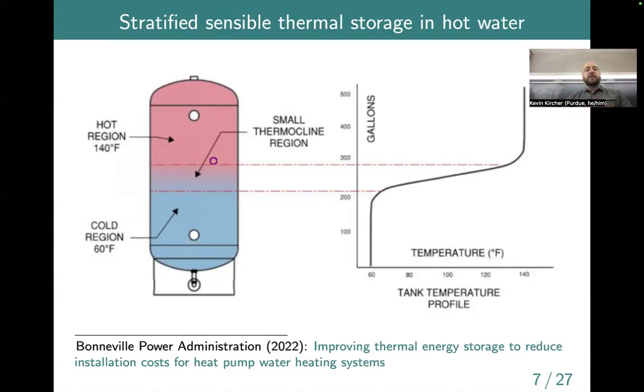And then I guess the other way is you can just have direct, basically, conduction. You have a cold layer and a hot layer, and they're touching each other. So you'd have heat flowing from the hot down to the cold. And so if the thermal conductivity of the substance is high, then I guess you would have more heat transfer and therefore more degradation of the stratification.